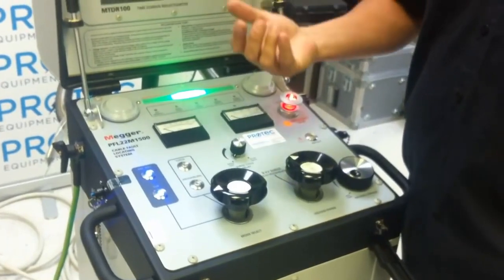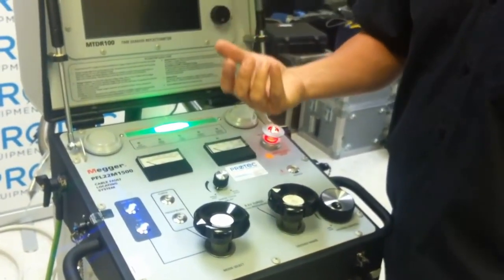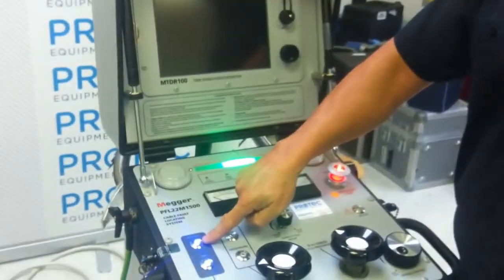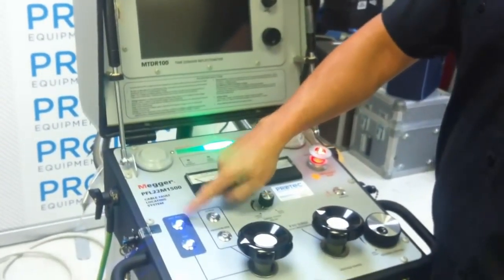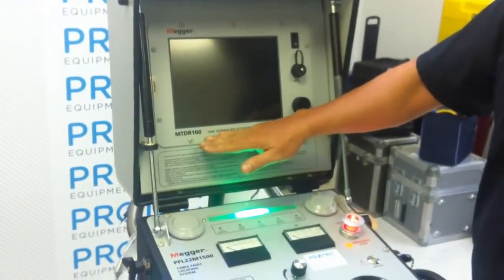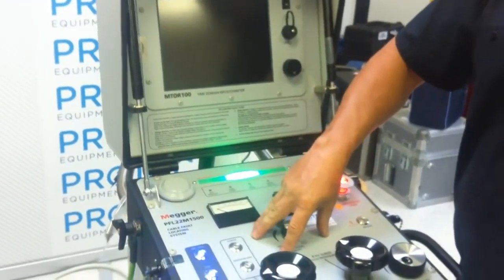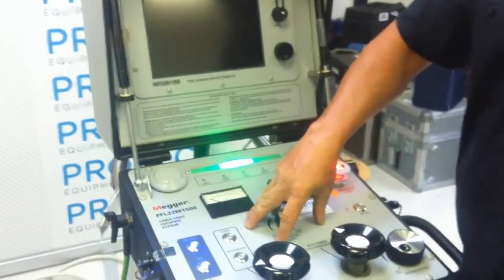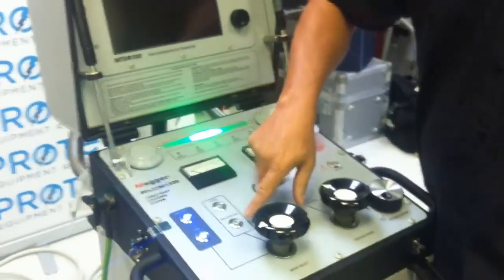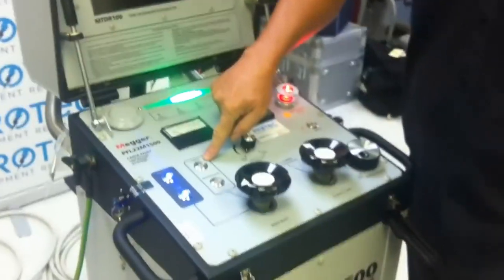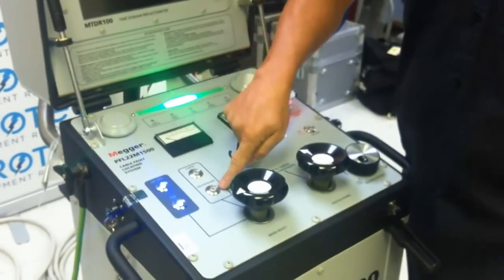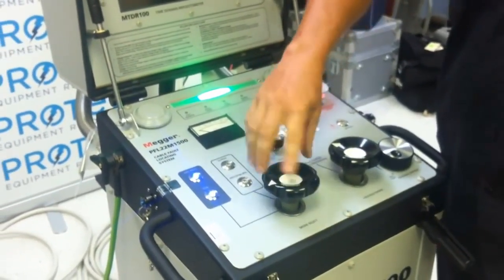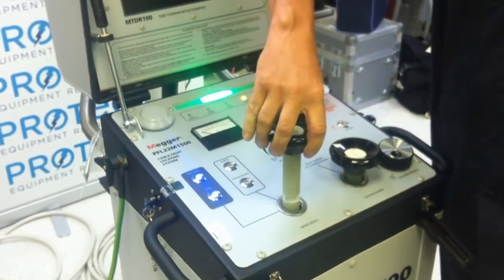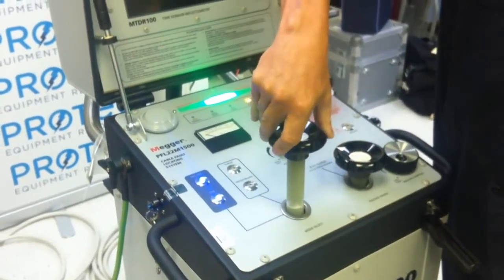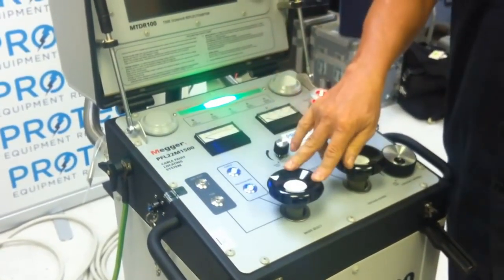If I'm doing a high voltage breakdown test and I want to be able to capture the point of where the cable flashed over, I would simply select the arc reflection mode. Again, it allows me to use the radar, allows me to use the high voltage surge generator simultaneously. If I want to change mode and I want to go to my direct functions of direct thumping or my proof burn mode, I simply lift up, rotate, and reset my switch.